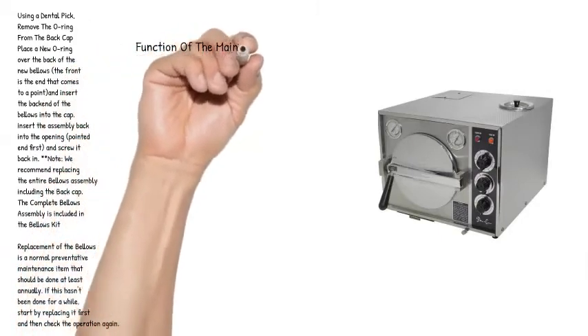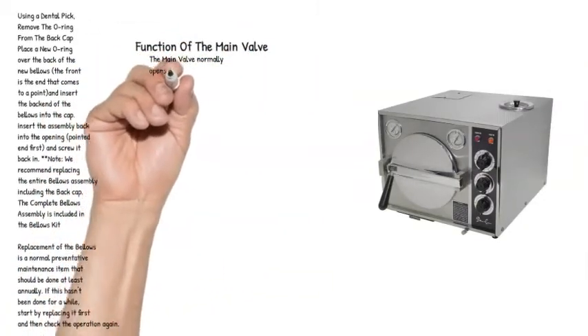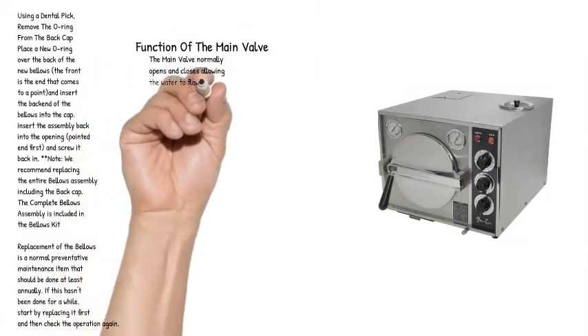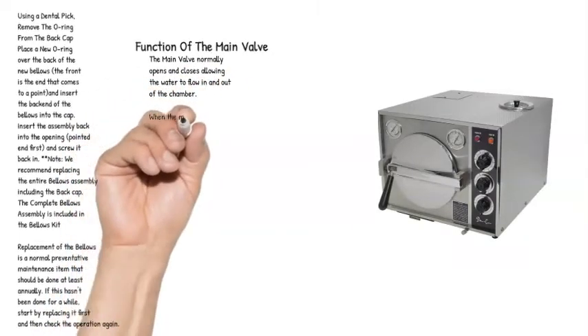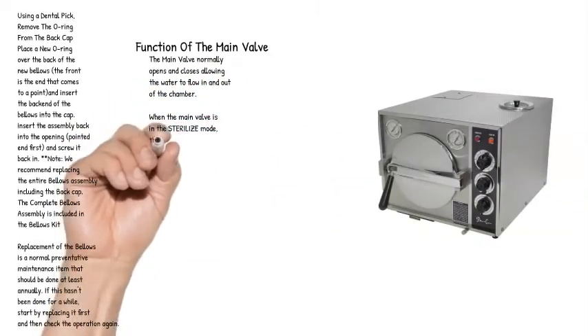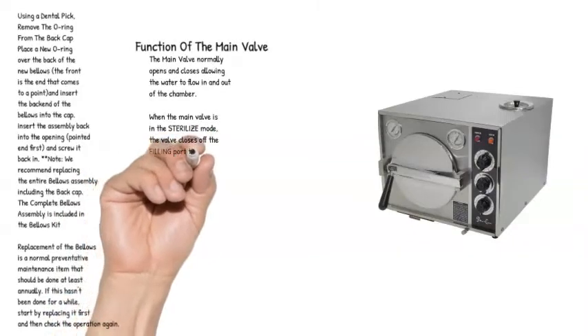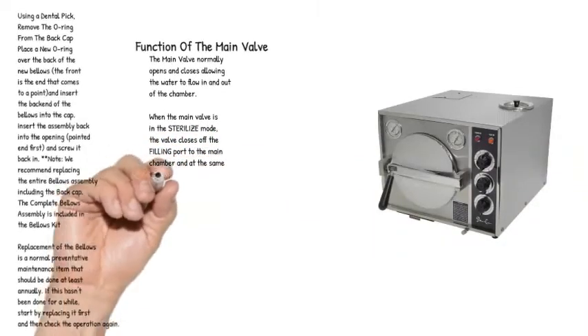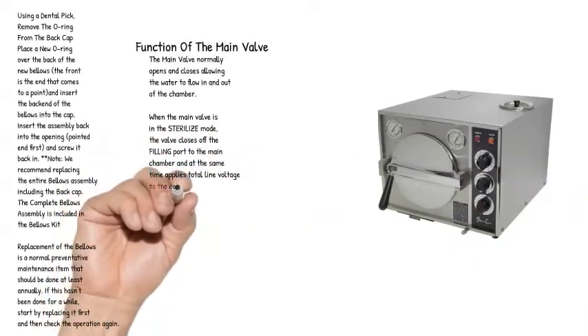Function of the Main Valve. The main valve normally opens and closes allowing the water to flow in and out of the chamber. When the main valve is in the sterilize mode, the valve closes off the filling port to the main chamber and at the same time applies total line voltage to the center heating element only.